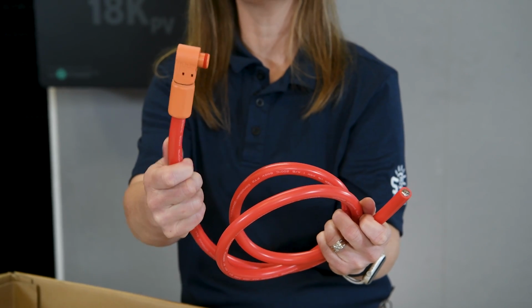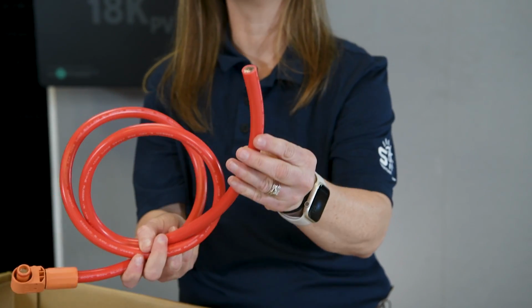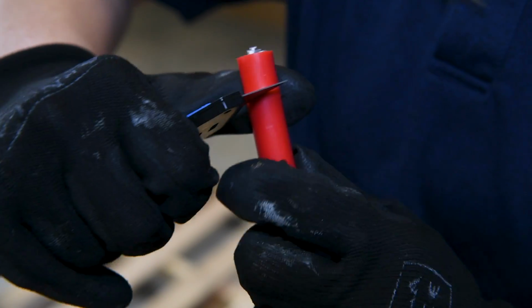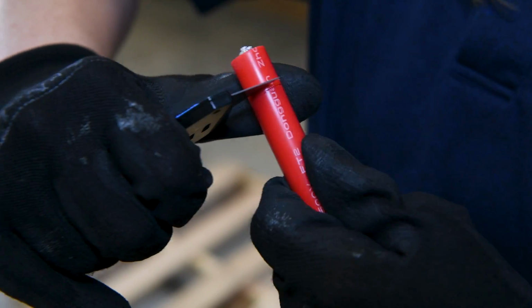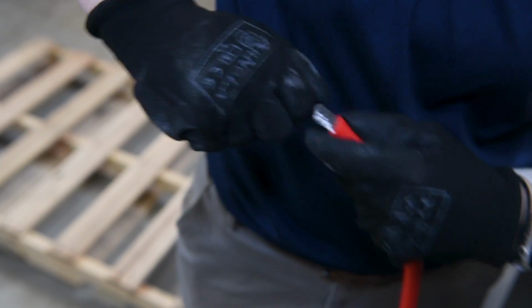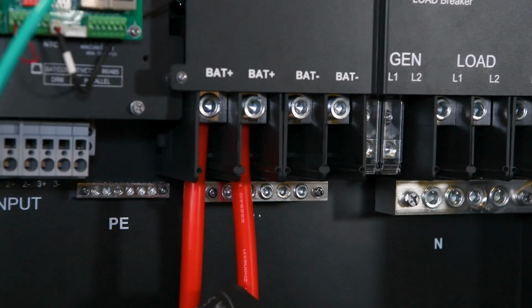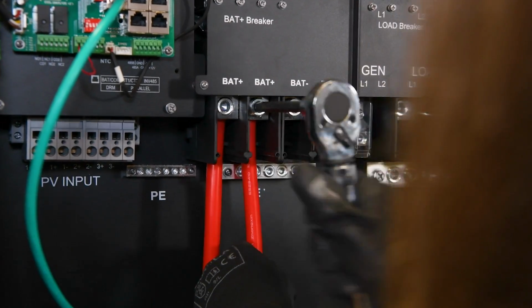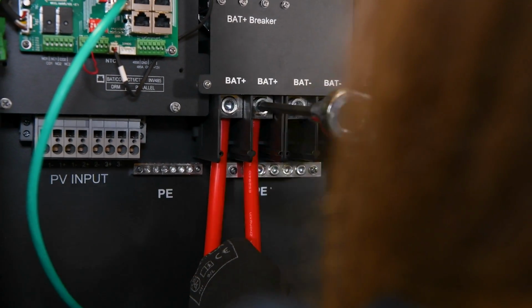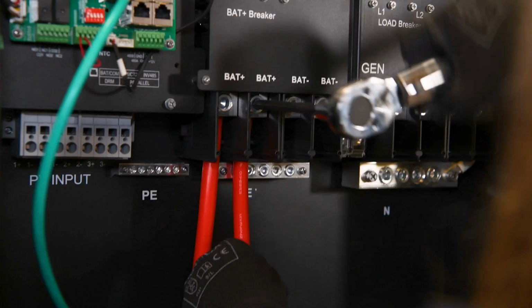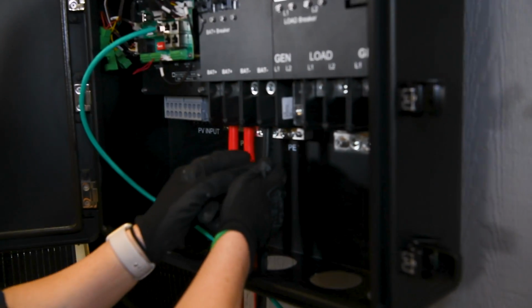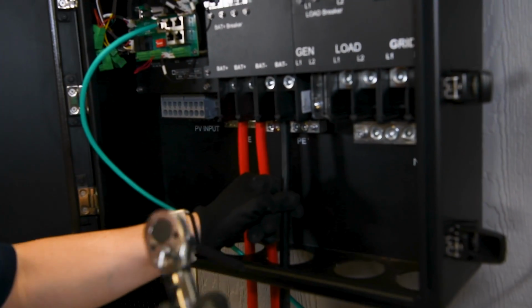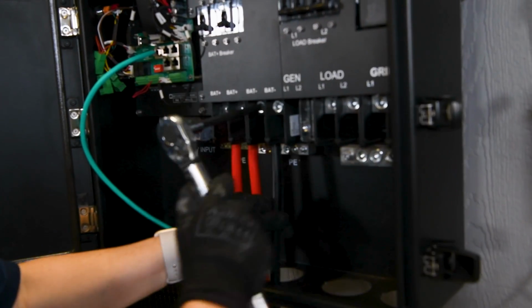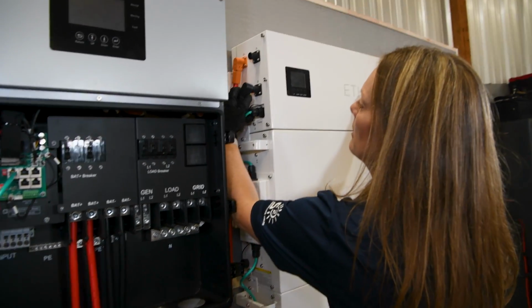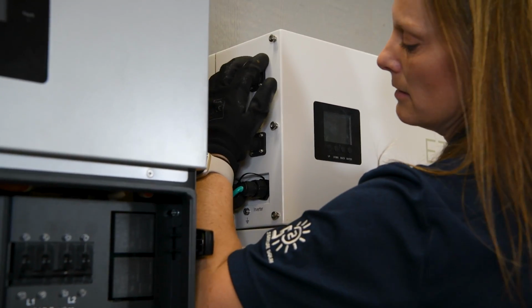Moving on to the power cables. These longer battery cables feature Amphenol connectors on one end and are insulated at the other. The insulated ends will need to be carefully stripped back about 3/4 inches before being inserted into the inverter. Once in place, they should be torqued down according to the inverter specifications, which is 165 inch-pounds for this 18K. We'll be using 2 sets of these cables because they're rated for 200 amps. This ensures our system is safeguarded against any surges that exceed 200 amps.